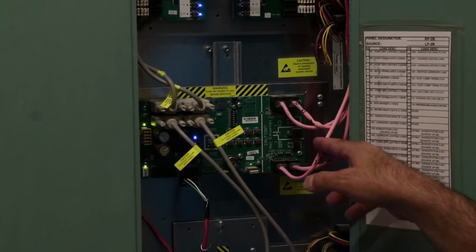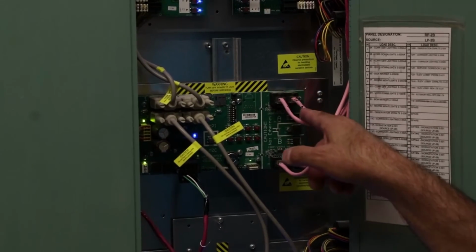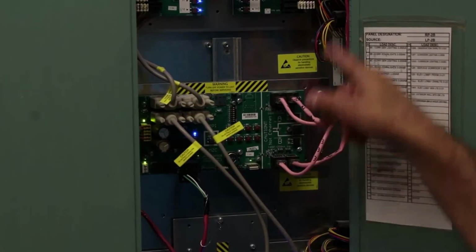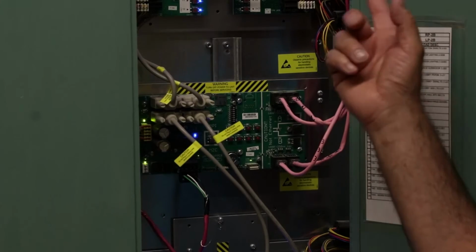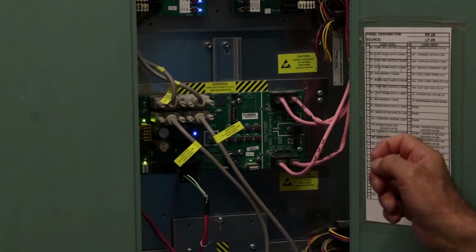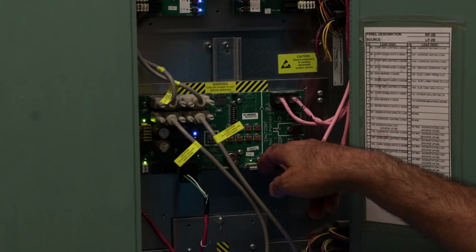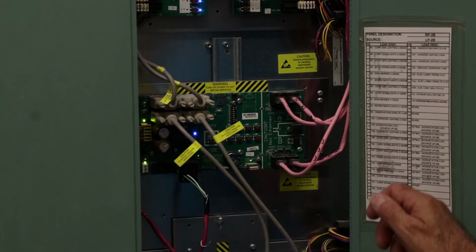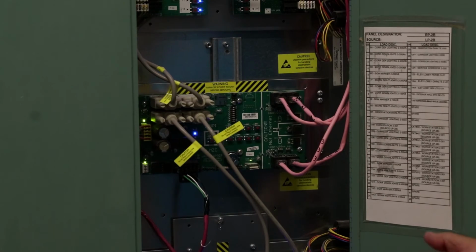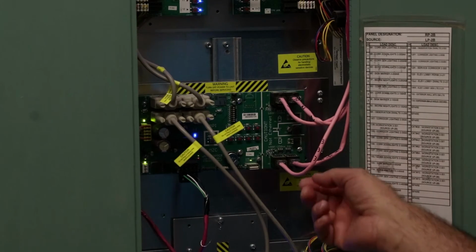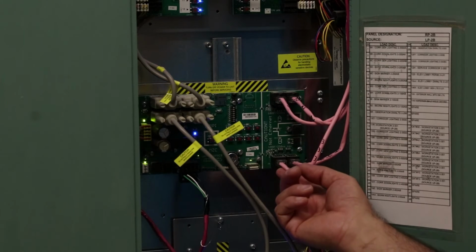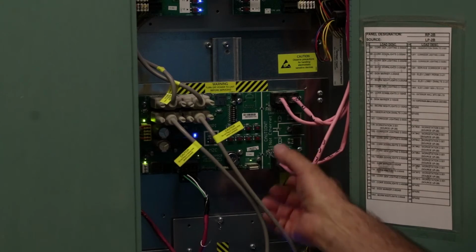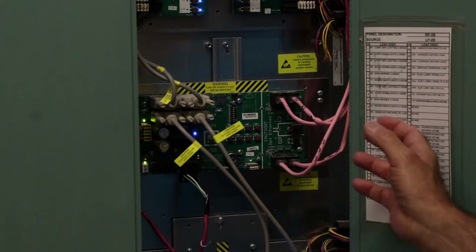What these cables are here is they are Ethernet cables, but they're not Ethernet. These are the cables that go out to all the switches and sensors throughout the corridor. And it even tells you here on the silk screen, caution, not Ethernet. So don't attempt to plug a computer in there to possibly read something. You're not going to get anything. There's actually voltage on here, so it may damage either the board or the computer, or both. So they just use the convenience of a Cat5 cable to interconnect everything.